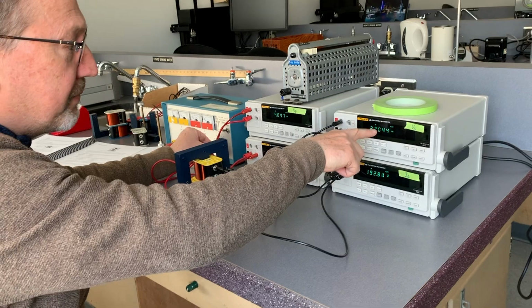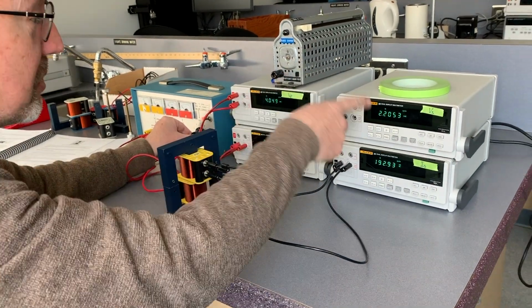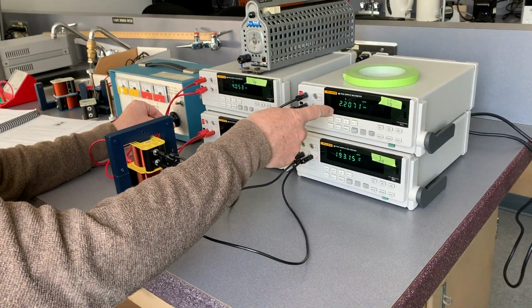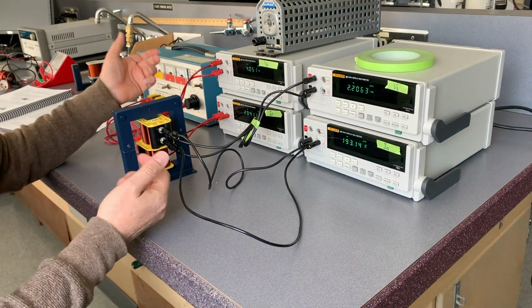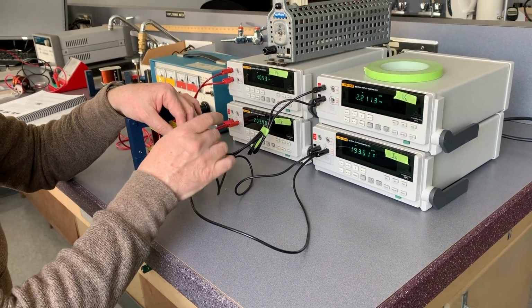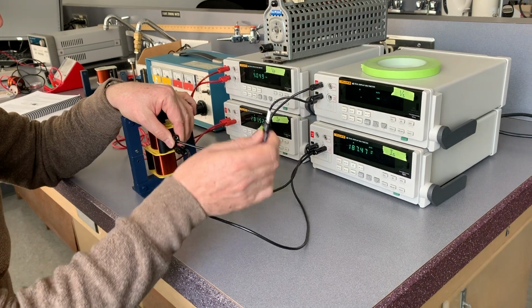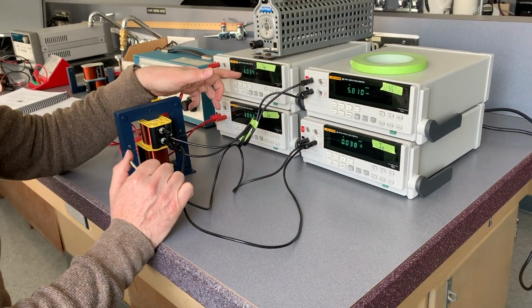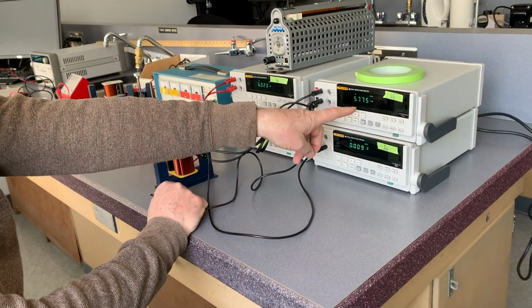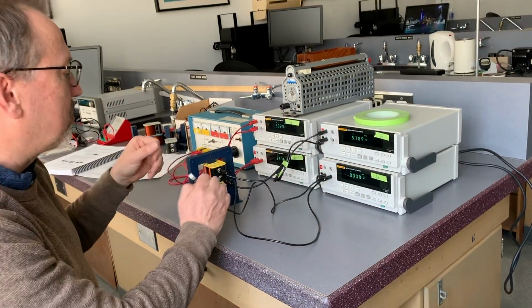We're not delivering 4 volts — we have 4 volts on the primary but not on the secondary, you can see the voltage has collapsed. If I disconnect the ammeter, here it goes — the primary voltage shoots up and the secondary voltage shoots up too, so it's almost back to 1-to-1.